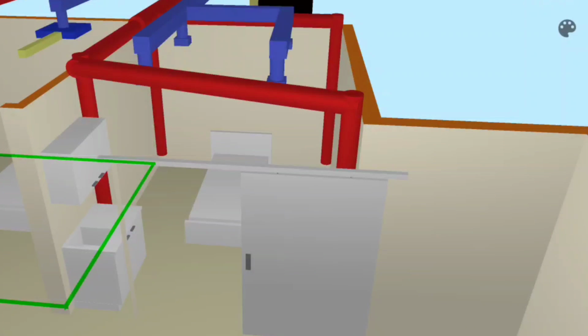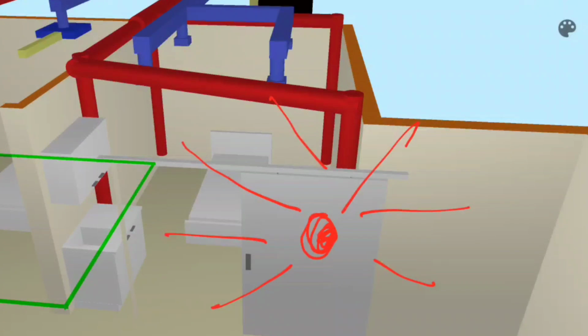very effective, because UVC light's effectiveness is determined by the inverse square rule. So meaning, if you have a UVC light source, and you can see that the lights go in different directions, the further you go from the light, the power of the light drops dramatically. So here you have pretty good effectiveness. The air that goes by close to the lamp is going to get disinfected. But as you go farther, you have to square the distance.